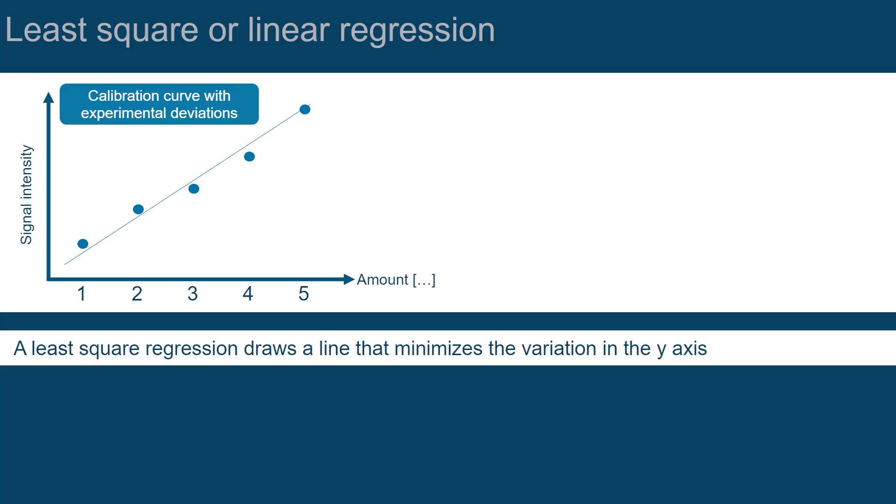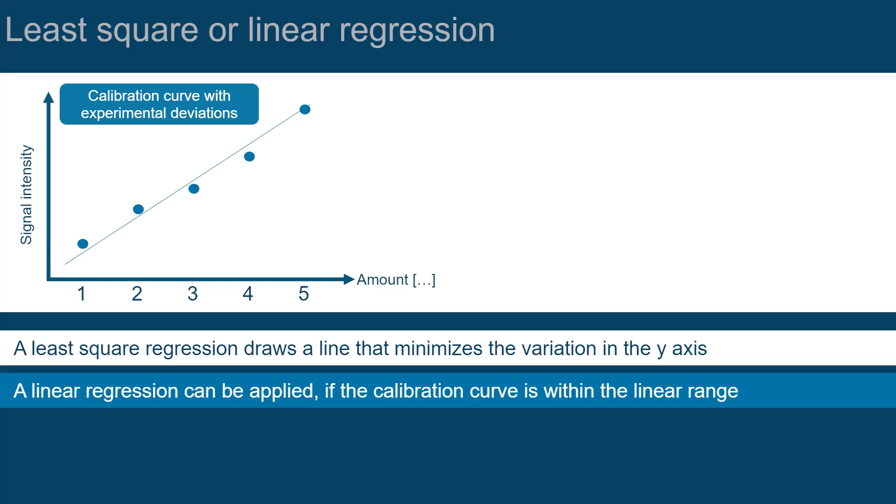Its purpose is to draw a line in a way that the variation in the y, or signal intensity axis, is minimized for all calibration levels. We can apply the subcategory of a least square regression, the linear regression, if the calibration curve is within the linear range.